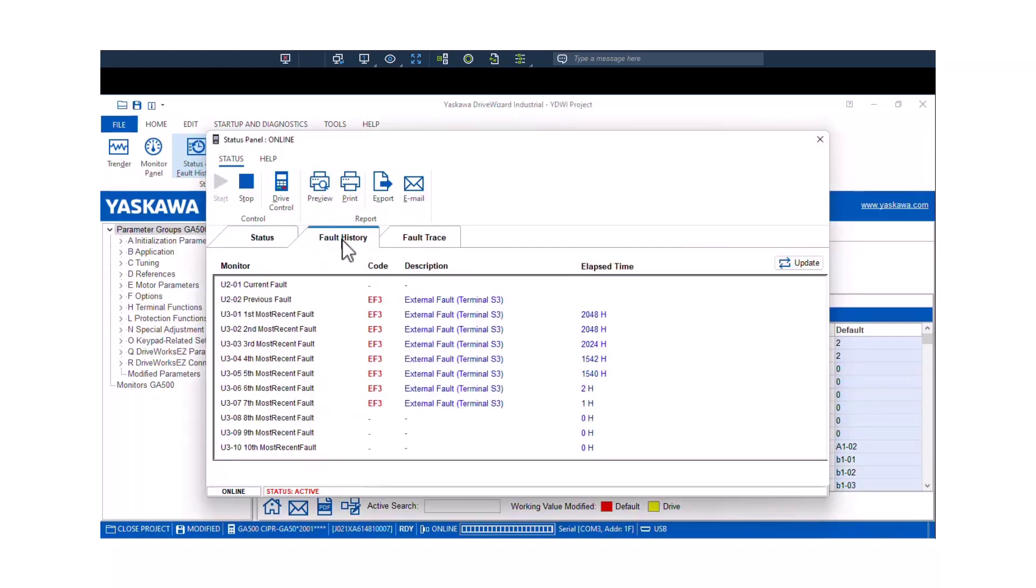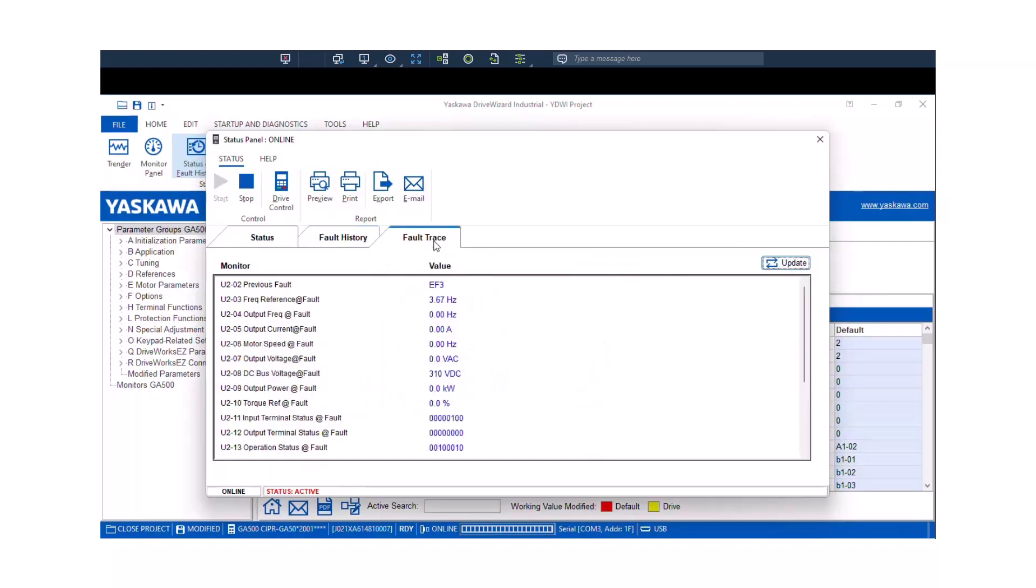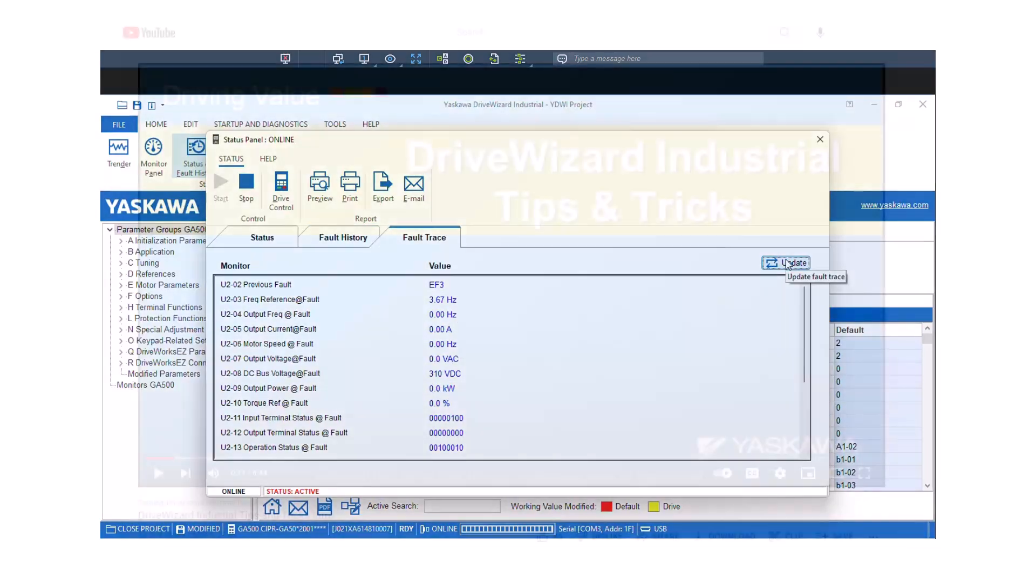Another nice thing you can do is you can view the full fault history. This will display the ten most recent faults in the drive. If you hit the Update to make sure everything is up to date in here, you can look and see what the current fault is. So if the GA500 faults, for whatever reason, this will display what the fault code is. This will be helpful since you guys can't see the keypad when you're operating this drive remotely. Also we have the fault trace, which will tell you what happened when the drive tripped out on that most recent fault.